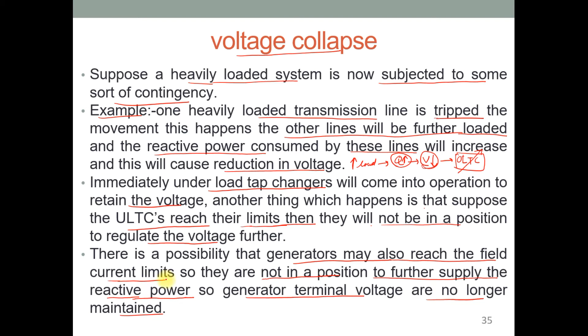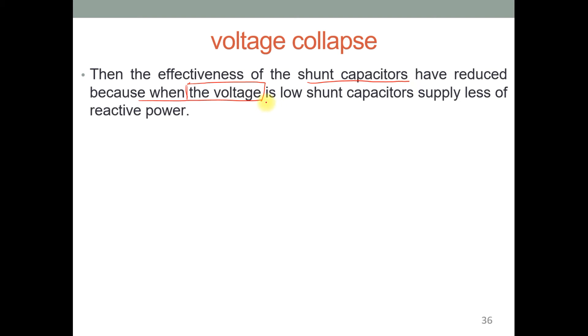Okay, so then the effectiveness, again let us consider from the compensating device side. Then the effectiveness of the shunt capacitors is reduced because the voltage is low. Yes, we know very well, just recall the characteristic of compensating devices. Clear? When the voltage is low, the effectiveness of the shunt capacitor to compensate the reactive power in the system is reduced because the voltage is low. So the low-voltage shunt capacitor supplies less reactive power.